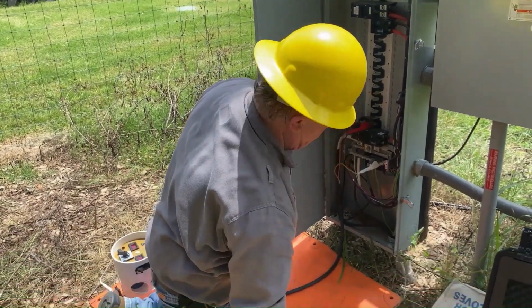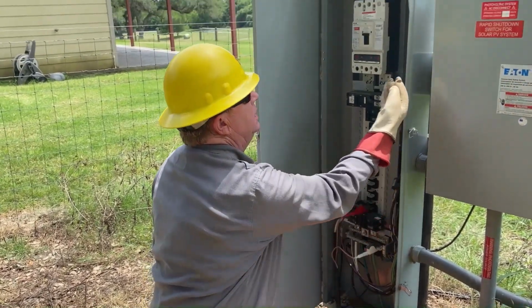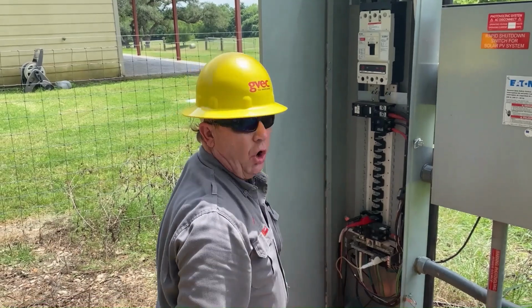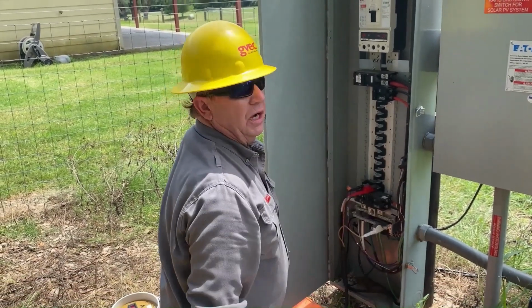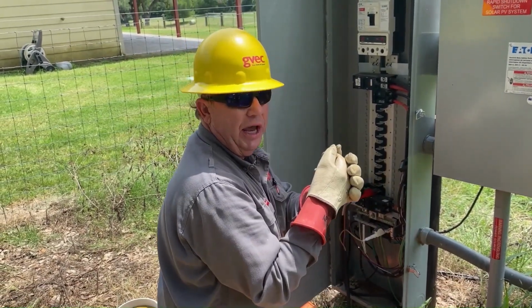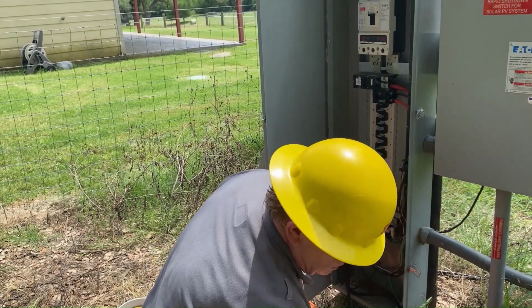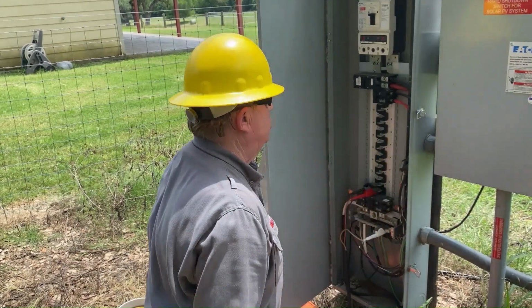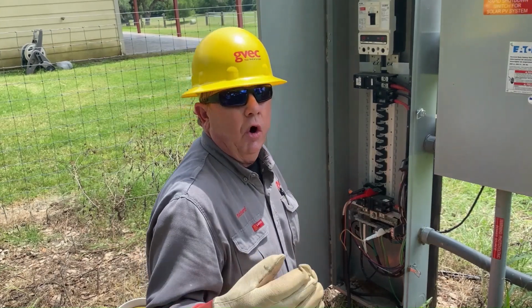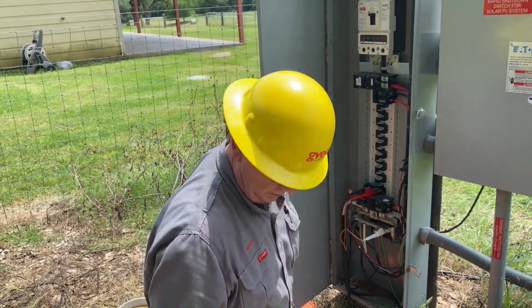Almost all of it is passing through the can, headed back to this lug that's scorched. On the back of that lug, where the lug bolts to that sheet metal can, it is scorched right now. So right now, that connector with 20 amps of neutral current is over 200 degrees Fahrenheit.